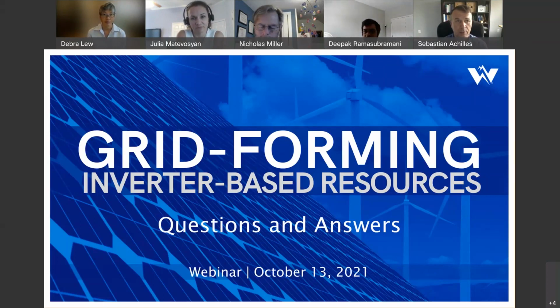I don't necessarily know that answer, but from the point of view of batteries, there seem to be options available that aren't too much more expensive than grid following batteries. But then we get into how many grid forming features do we need? What is the rating? What do we want this resource to do transiently? How much ride-through support? Depending on those questions, the cost will change, and all of those are grid forming. So there's a price for each one of those grid forming specifications. I don't know the price for any of them, but in batteries it's probably not too different from grid following.